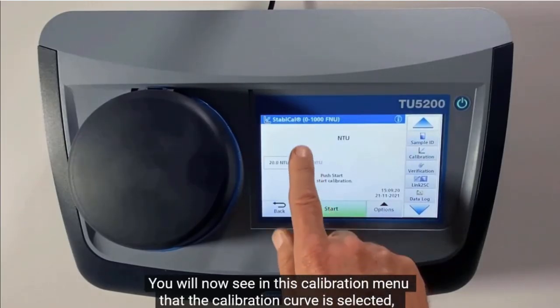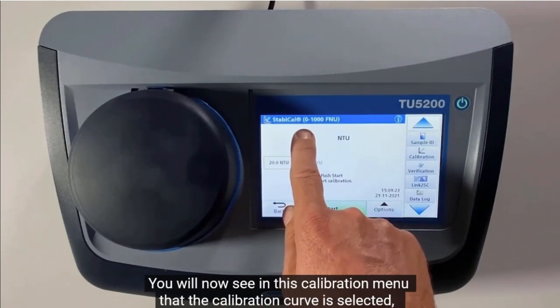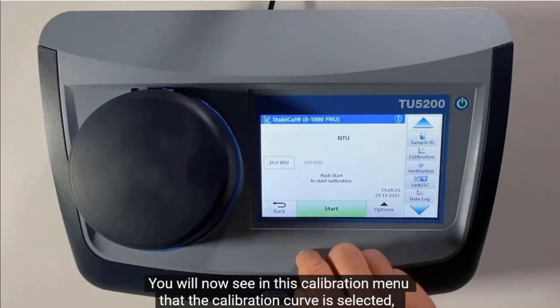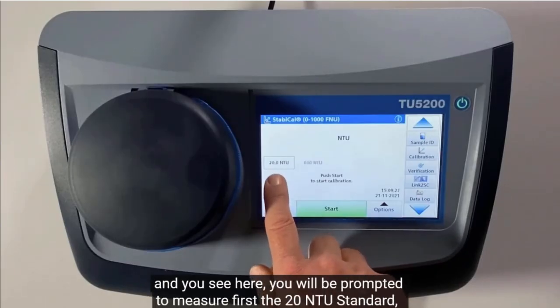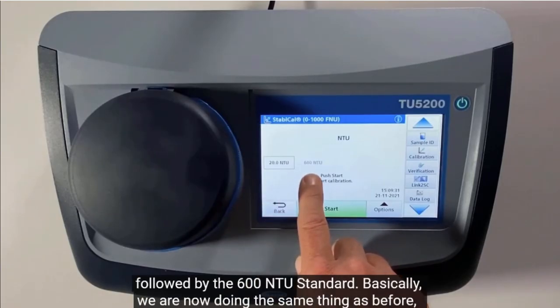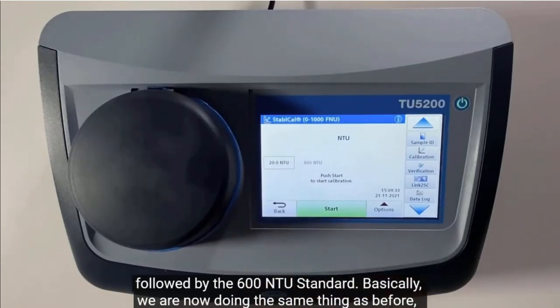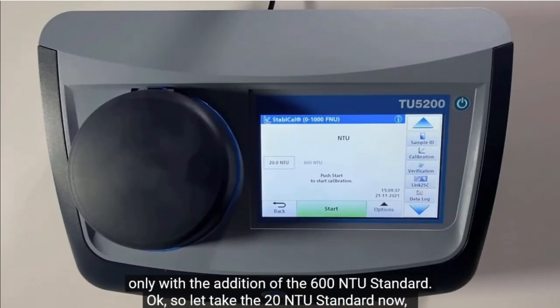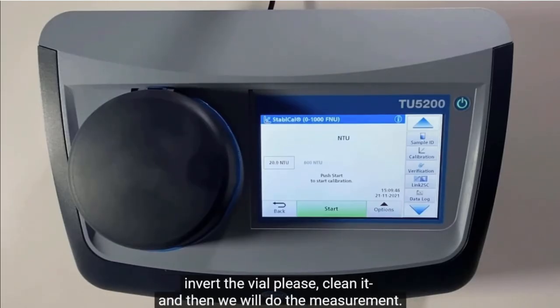You will now see in this calibration menu that the calibration curve is selected, and you will be prompted to measure first the 20 NTU standard followed by the 600 NTU standard. Basically, we are now doing the same thing as before, only with the addition of the 600 NTU standard. Okay, let's take a 20 NTU standard now. Invert the vial, please, clean it, and then we do the measurement.